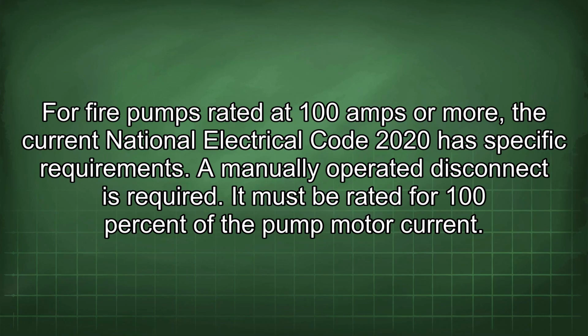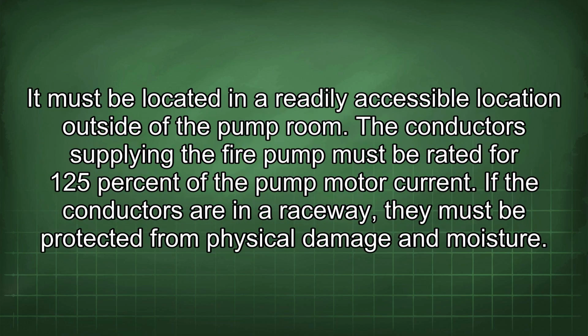For fire pumps rated at 100 amps or more, the current National Electrical Code 2020 has specific requirements. A manually operated disconnect is required. It must be rated for 100% of the pump motor current. It must be located in a readily accessible location outside of the pump room.